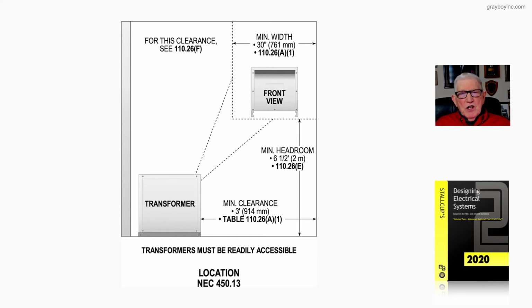But this is the general rule of 450.13 for locating transformers, and it doesn't matter if it's on grade level or it's hanging from the ceiling or a rack or whatever it may be. You still have to have these clearances, except above a suspended ceiling, which we'll get into later. But you need to review 450.13 and see what the requirements are there for transformer location and where such clearances are required. And that's what this figure 20-4 is illustrating.